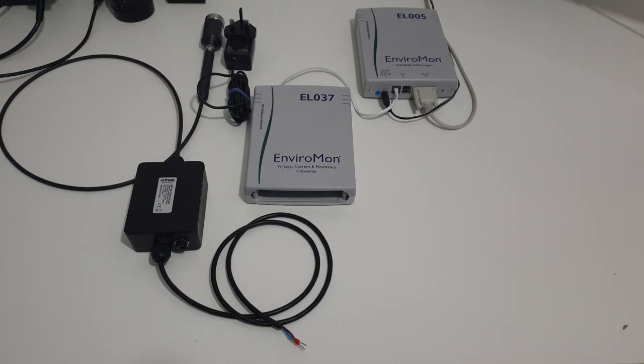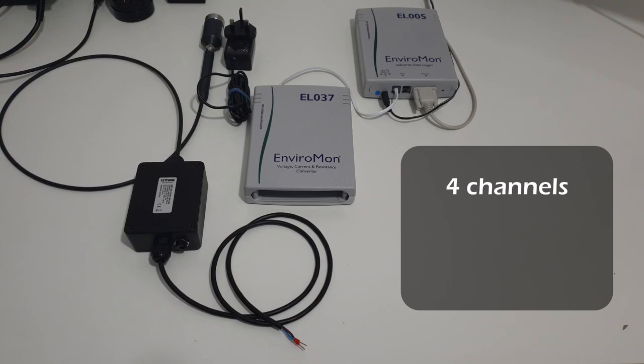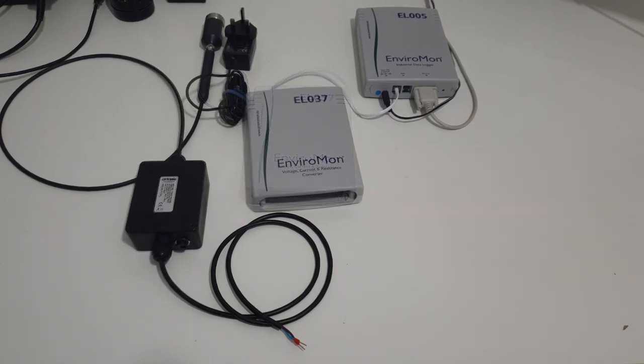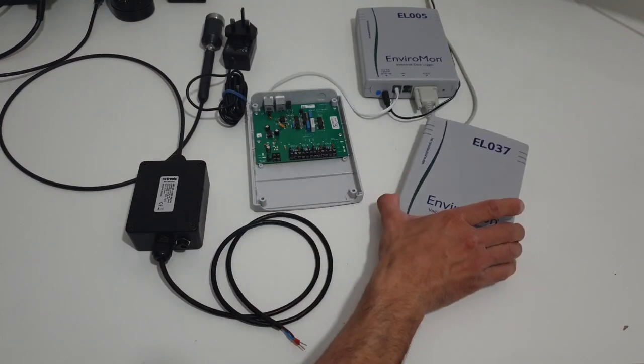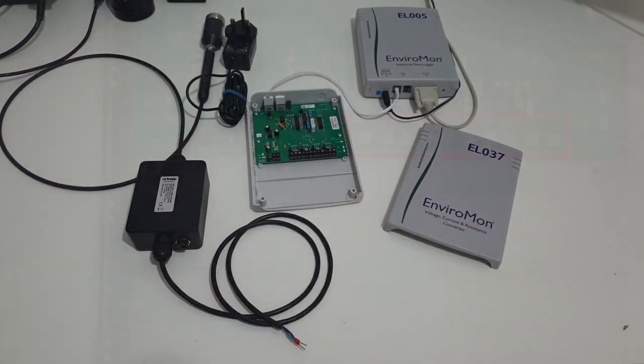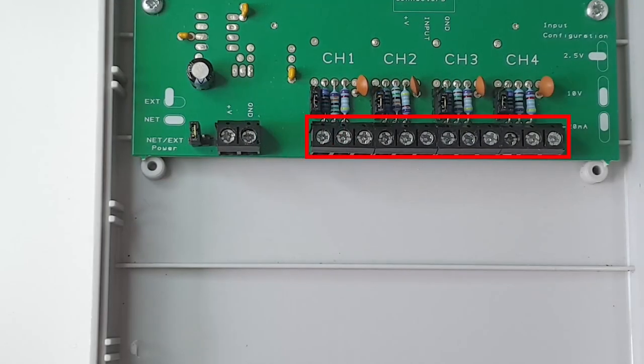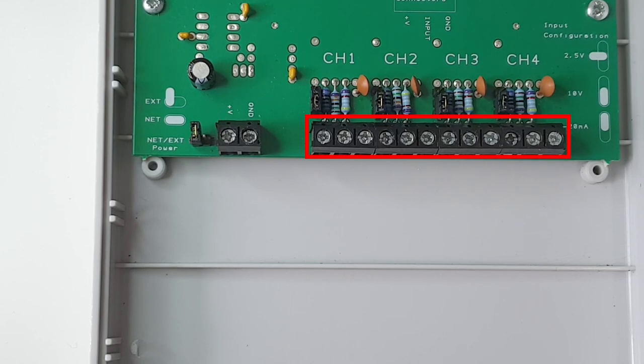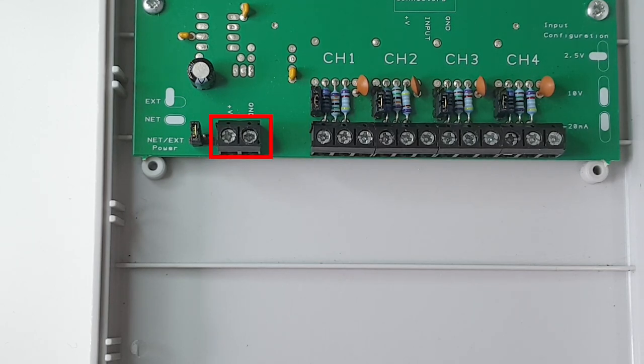The EL037 has four channels, each can be configured in three ranges: 4-20 milliamp, plus or minus 2.5 volts, and plus or minus 10 volts. If we take the cover of the EL037, you'll see that we have a number of screw terminals for each of the channels and also a screw terminal for the power supply if you wanted to power your sensors.